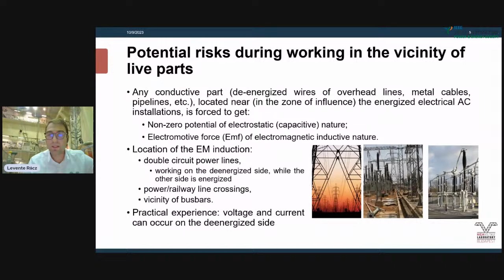This is important because of safety aspects. We did some simulation and also some field measurements in Hungary, and you can see here a 400 kV power line tower. We did some modeling and simulations, and you can see that in the different phases, the maximum induced voltage could reach almost 20 kV, which is very, very high. In this way, we have to make some proper protection against the induced voltage.